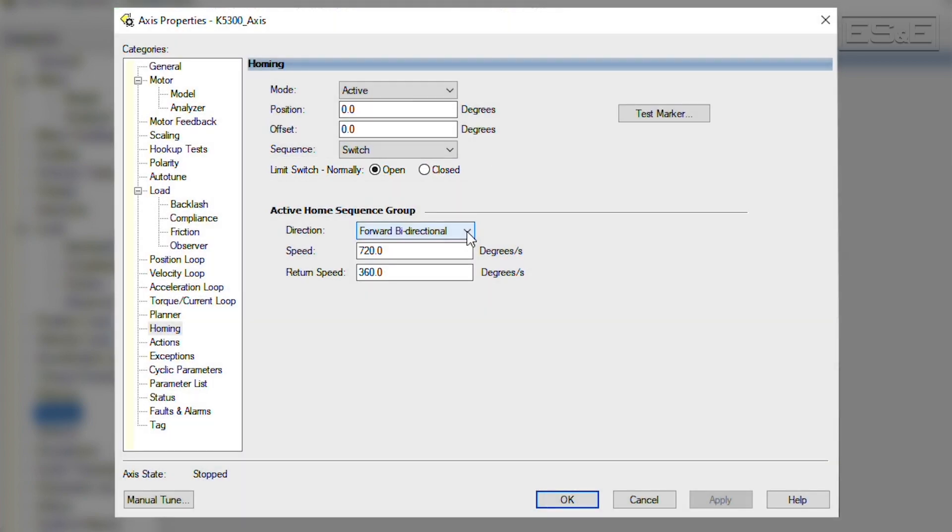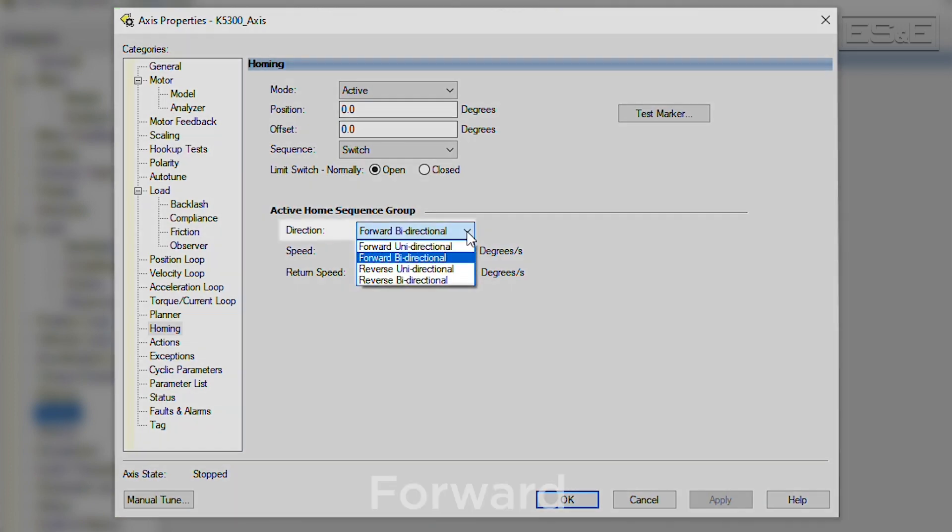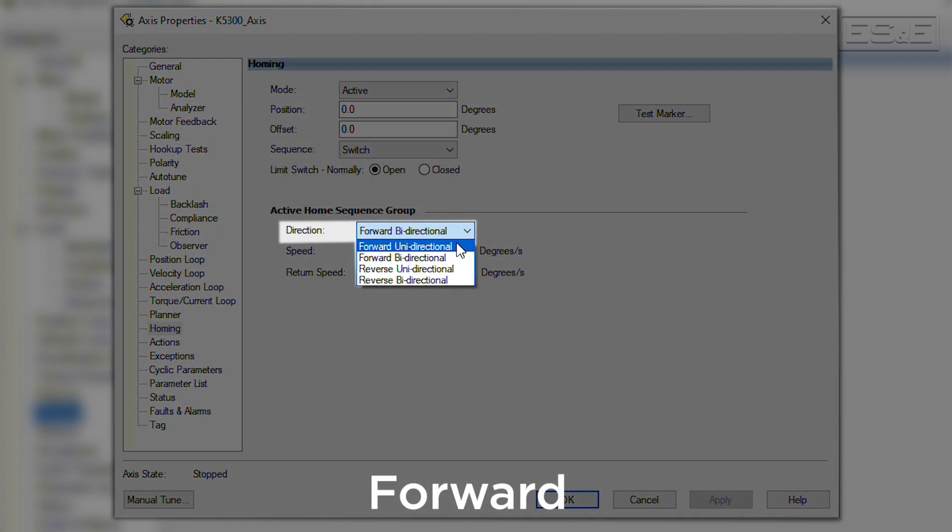For active homing, there are some additional configurations that define how the servo will move towards the home switch or marker pulse. If forward is selected, then the servo will move in the forward direction during the automatic homing sequence in order to find the home switch.